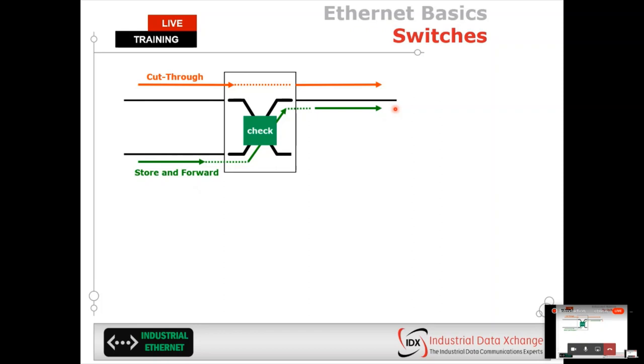How things might be damaged or changed would be faulty device interfaces, or interference by high voltage cabling, which I said you should prevent a little bit earlier. These could change the PROFINET or Ethernet message in some way. The store and forward technology would check that the CRC does not align properly with what the message should say, and he'll delete that message.